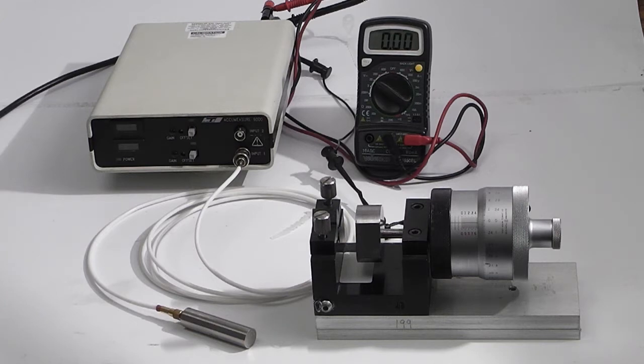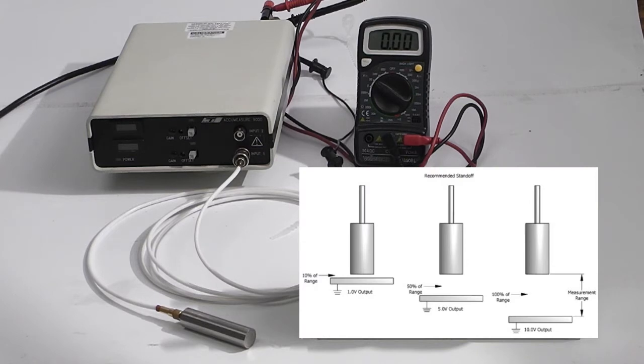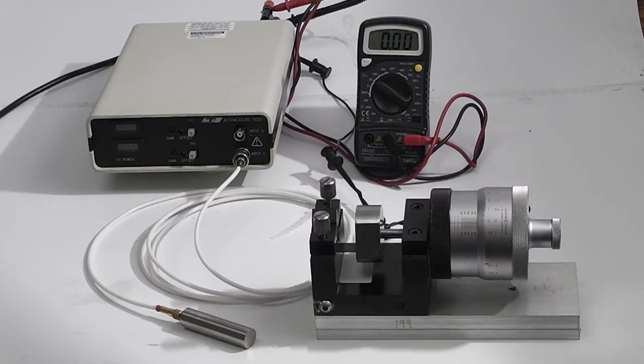range of 2.5mm. The AS9000 demo system is supplied with two ASP 100 CTA probes which have a basic range of 0 to 2.5mm, so no range extension within the amplifier is needed. The upper end of the range is 10 volts DC, which corresponds to 2.5mm, but sometimes it can be used up to 11 volts. However, we guarantee our accuracy up to 10 volt DC full scale, and this is shown in the supplied calibration curve. Our linearity with this system is better than plus or minus 0.01% full scale range.